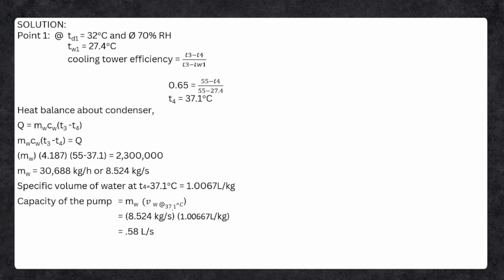So we use the formula for heat, Q equals mCp delta T. We substitute the values, and since we don't have the mass value, that's what we'll solve for. Substitute Cp as 4.187, T3 as 55, and T4 as 37.1, then solve. The value of heat equals 2,300,000. Computing that, we get the mass of water as 30,688 kg per hour or 8.524 kg per second.